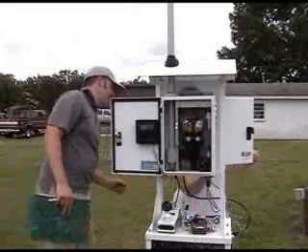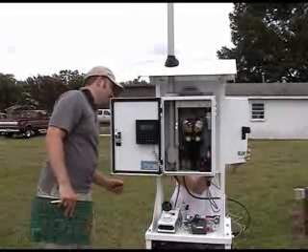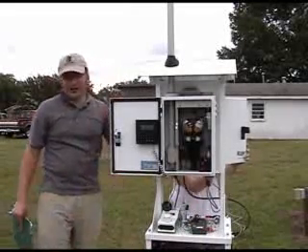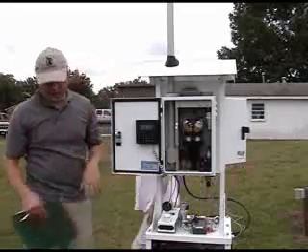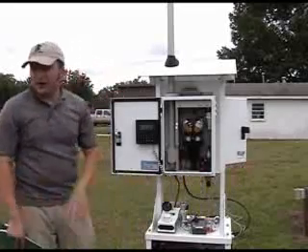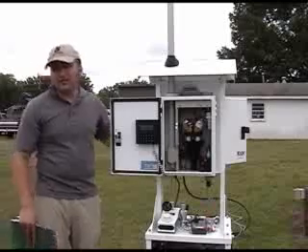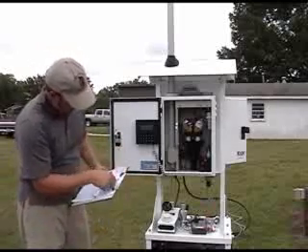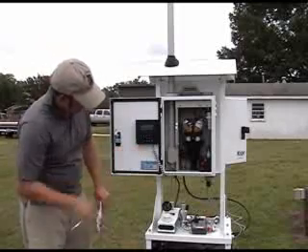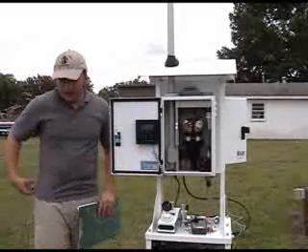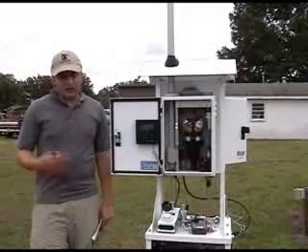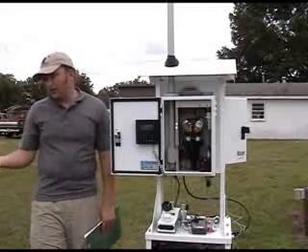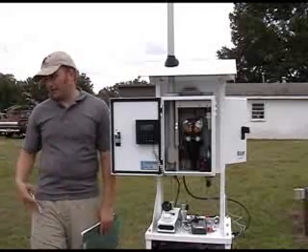Oh, okay. And all this site config is something you typically just do the first time. Just do it once and it'll be saved. Yes, and it doesn't matter if you turn the power off or anything like that. It's saved in the controller. So 0758. I'm sure something can happen though where you have to put it back in. Well, for example, if your controller gets fried and they send you a new one, then you'd have to reprogram that controller. You'd also have to go through all the calibration and stuff like that again.